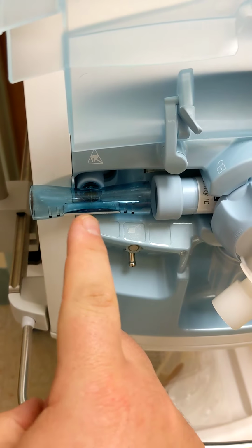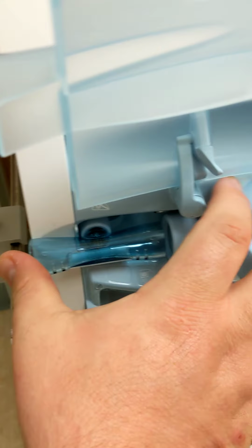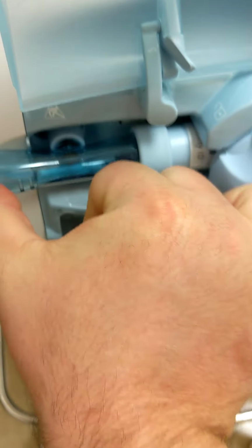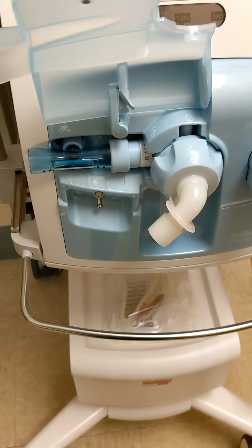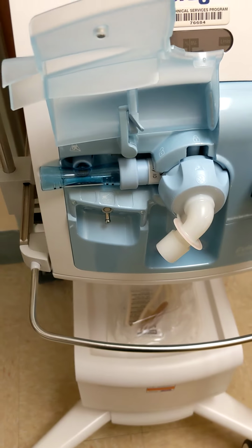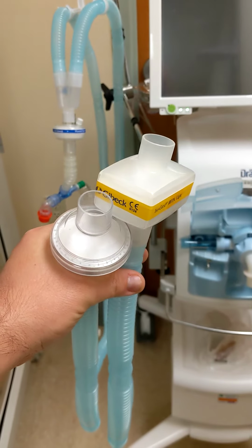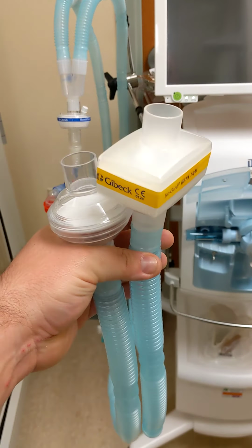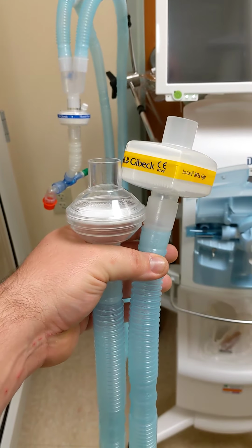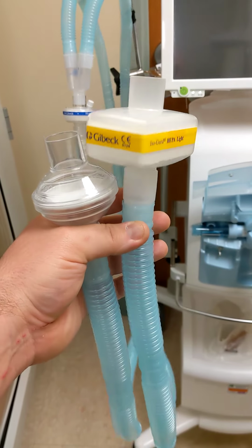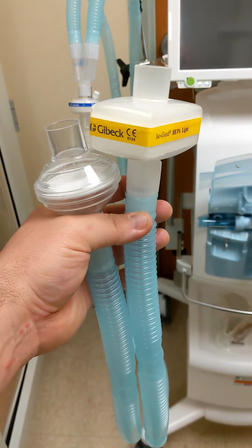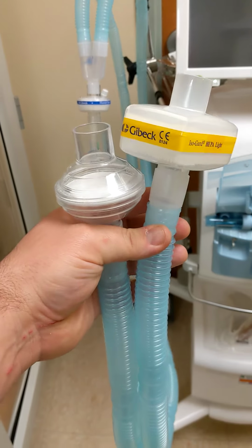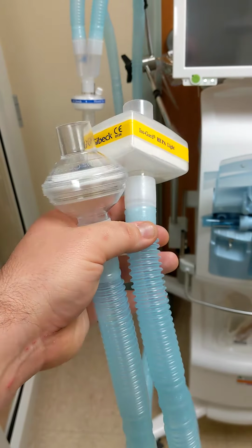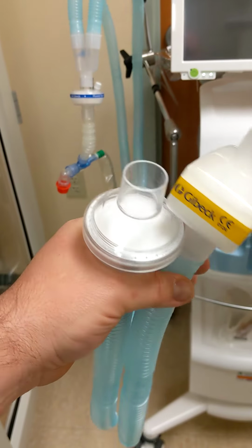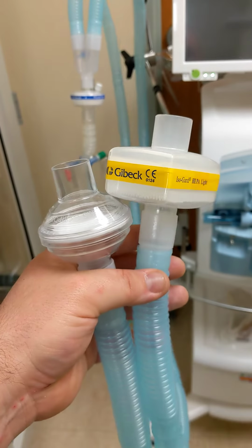Now the next step would be to connect the two. You slide this over, and it is now connected. Now we have the vent limb. On the end of each one, you will put the class 13 filter, which is yellow. It's a HEPA filter. And then you will put a ViroBac on the inspiratory side. It doesn't matter which direction you put it on, just one of each.